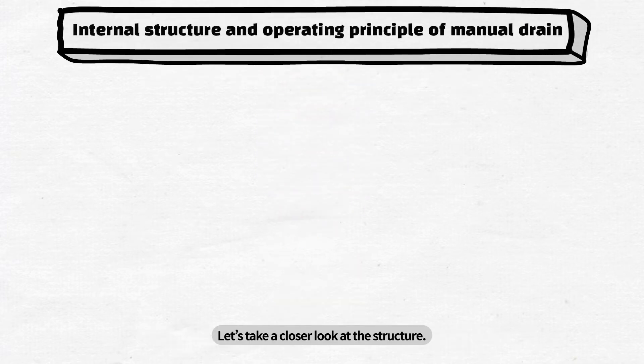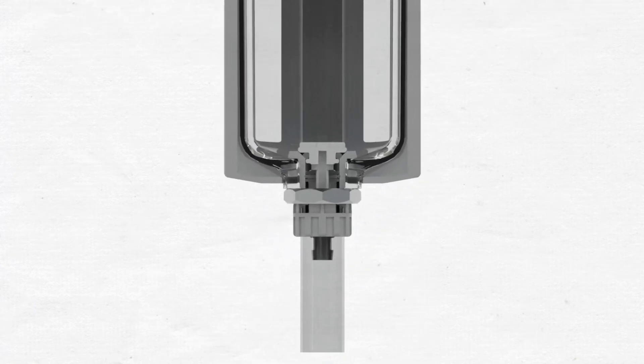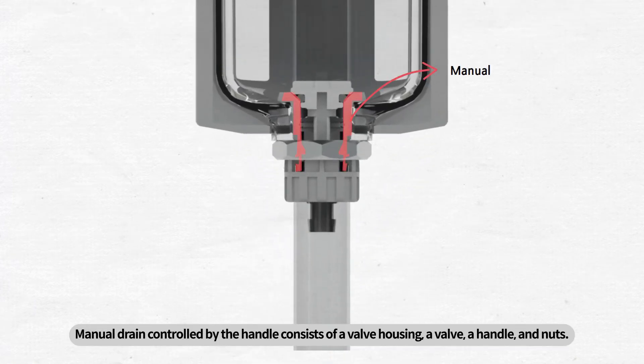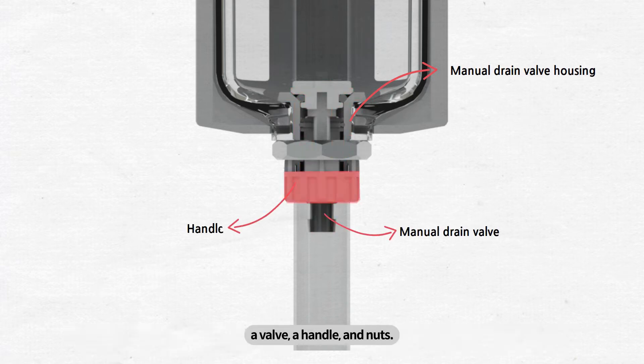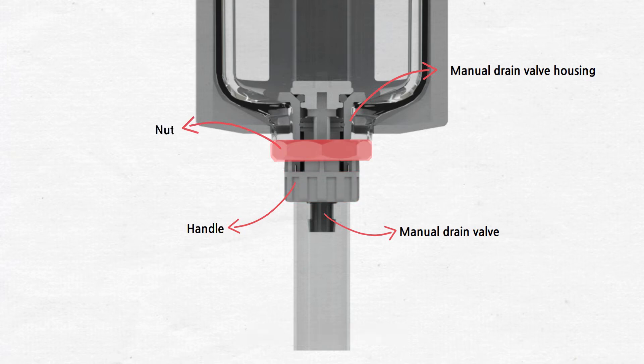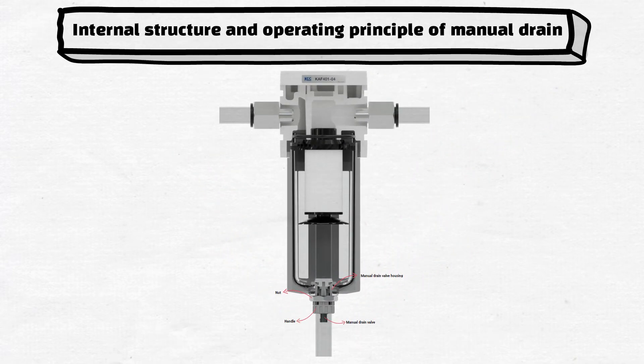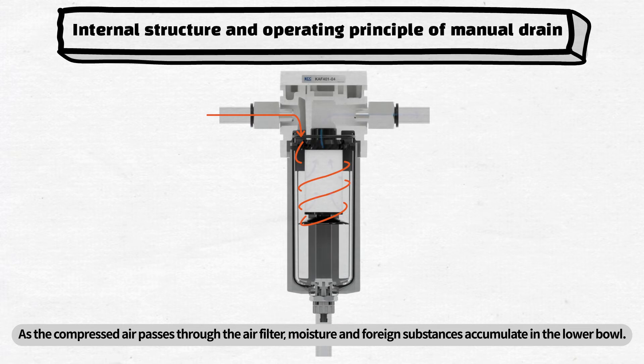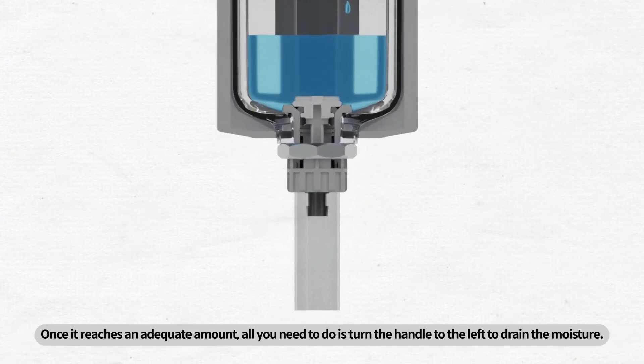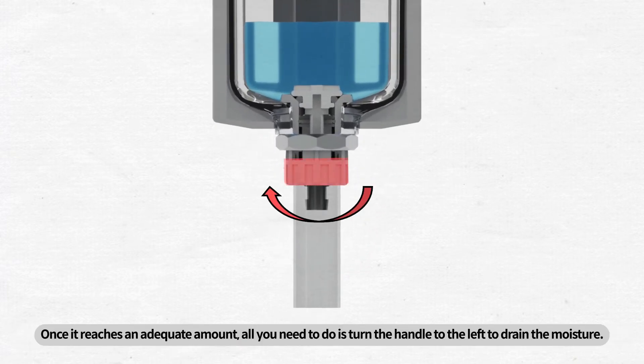Let's take a closer look at the structure. Manual drain controlled by the handle consists of a valve housing, a valve, a handle, and nuts. I'm going to show you how these components work one by one. As the compressed air passes through the air filter, moisture and foreign substances accumulate in the lower bowl. Once it reaches an adequate amount, all you need to do is turn the handle to the left to drain the moisture.